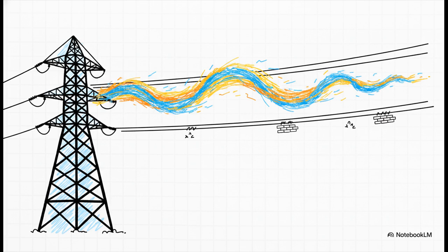And quick check, how do you raise a line's SIL to push more power without rebuilding the towers? You bundle the conductors. Running 2 or 4 subconductors per phase increases what we call the geometric mean radius, or GMR. That lowers inductance and raises capacitance, pushing the SIL higher. It's a direct design trade-off with the geometric mean distance, or GMD, between the phases. This is exactly why those massive 400 kilovolt plus lines almost always use bundled conductors.